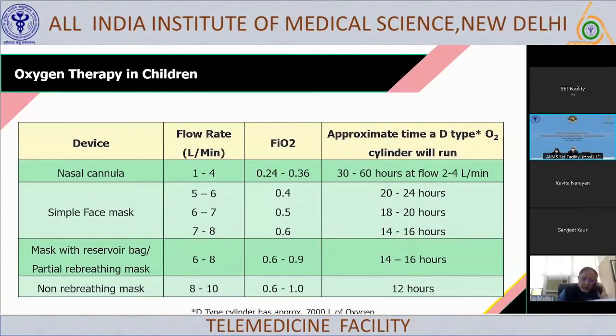And we also need to have an idea that if we have a D-type cylinder, then this is likely to run for 30 to 60 hours if the flow rate is 2 to 4 liters per minute. So if it's 2 liters, then about 60 hours; at 4 liters, it would be over in about 30 hours. So that's important to plan how many cylinders you need or when you need a replenishment.